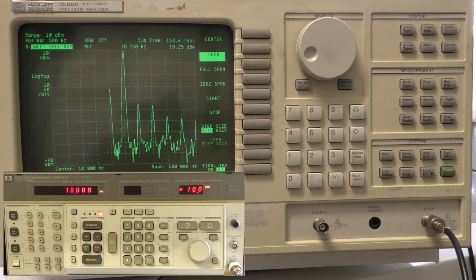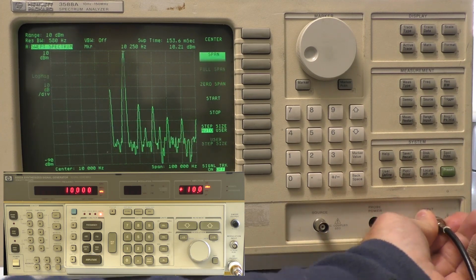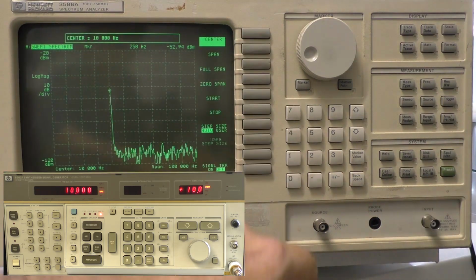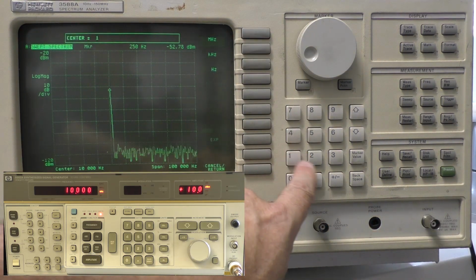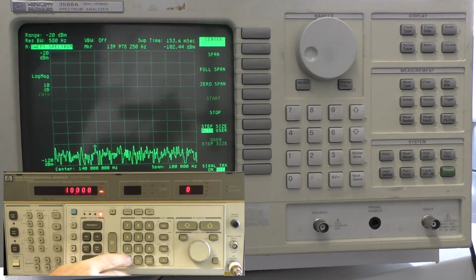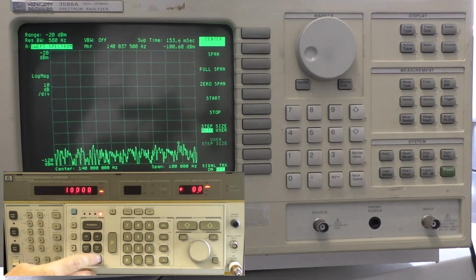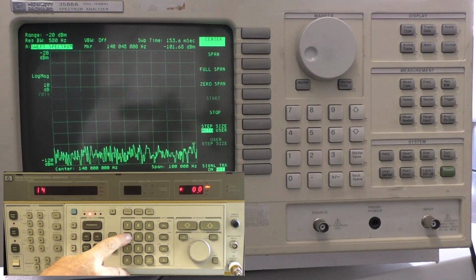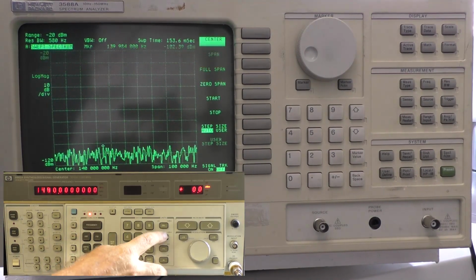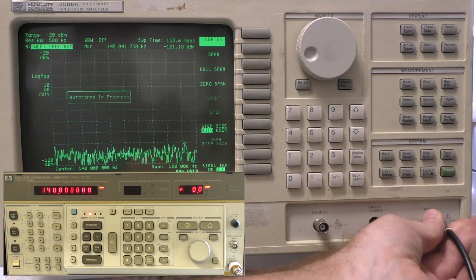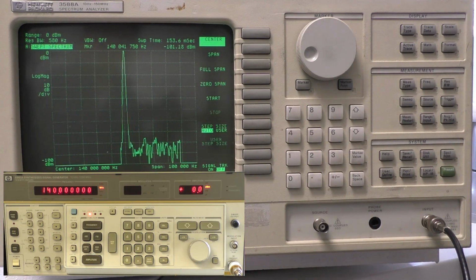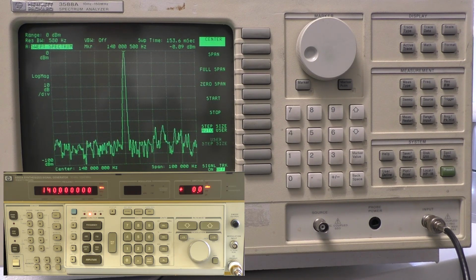Let's check the upper range. Unplug the signal. Hit center. Set the center frequency to 140 MHz. Set the signal generator to 0 dBm. The frequency to 140 MHz. Plug the generator into the input. The auto range kicks in. The unit has detected the 140 MHz signal at -0.09 dBm, pretty good.